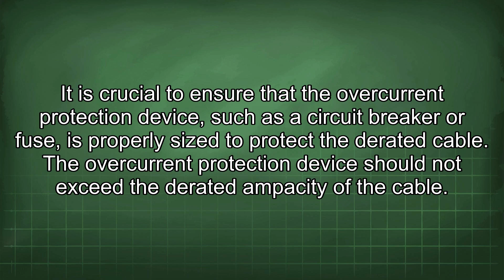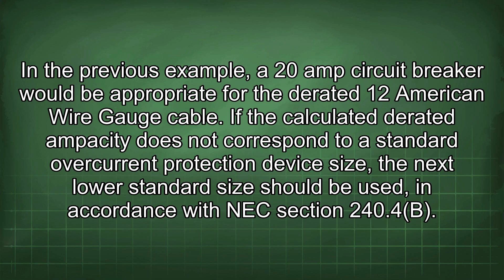The overcurrent protection device should not exceed the derated ampacity of the cable. In the previous example, a 20 amp circuit breaker would be appropriate for the derated 12 American wire gauge cable. If the calculated derated ampacity does not correspond to a standard overcurrent protection device size, the next lower standard size should be used, in accordance with NEC section 240.4(B).